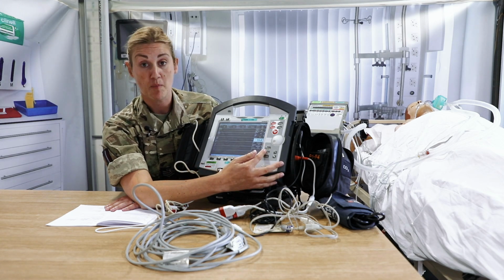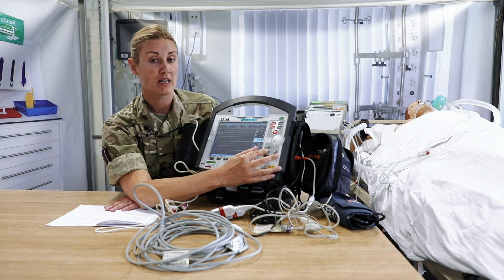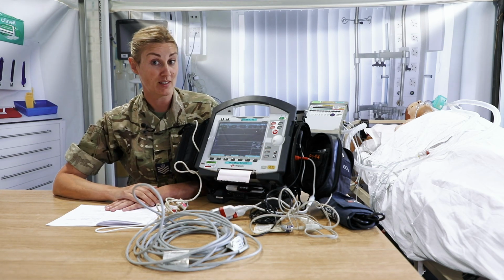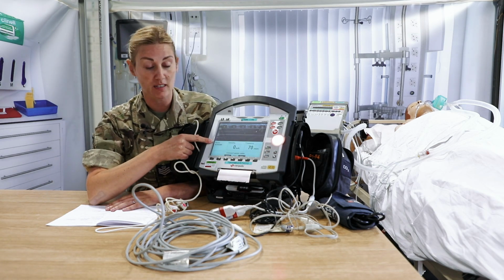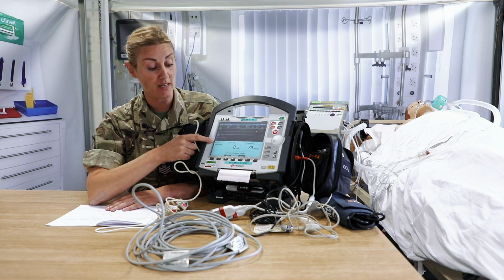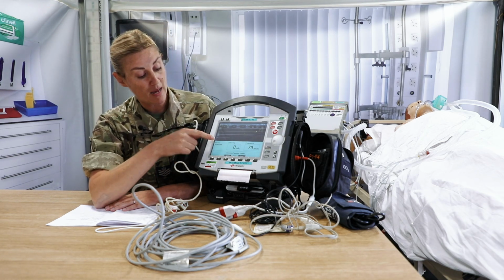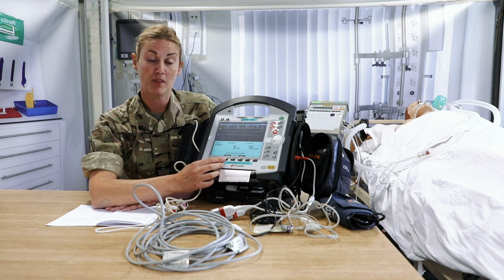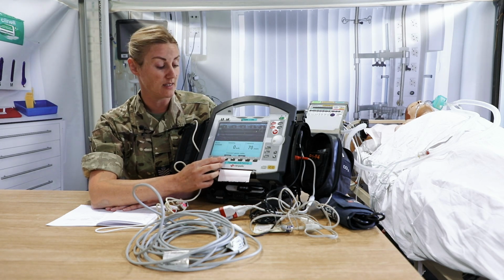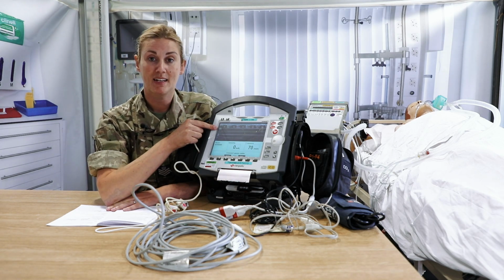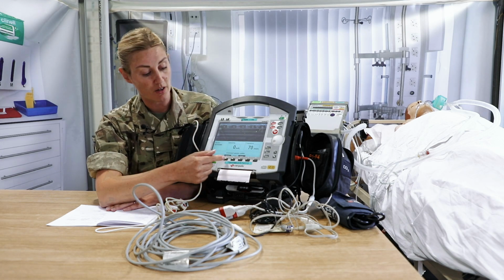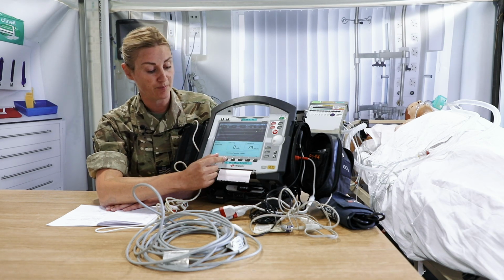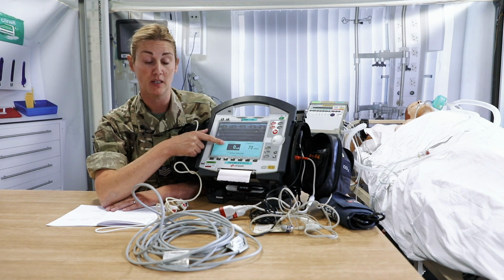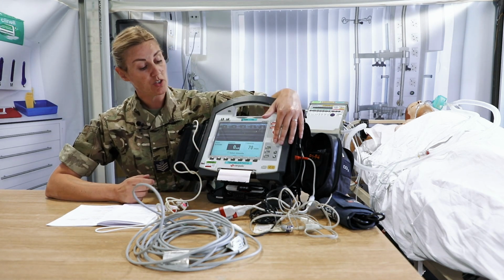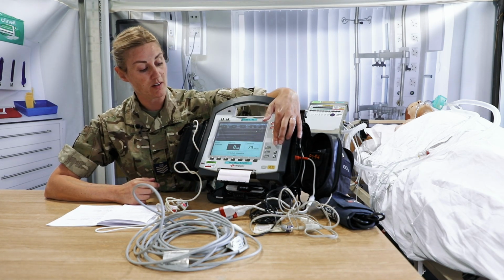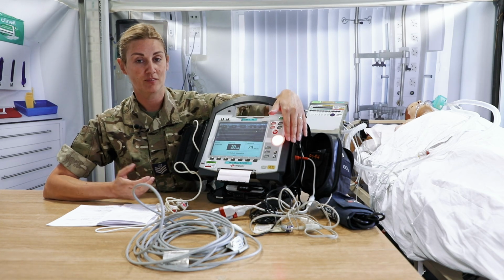Our next button is our pacer function. We're going to test that by pressing the pacer function, and you'll see that pacer comes up. It automatically comes on in demand mode, and all we're going to do is confirm that when I start dialing in an intensity, that the ECG recognises that the pacer is connected. So if I press this intensity button, our milliamperage becomes available. I'm just going to use the jog dial to start dialing in some milliamps.